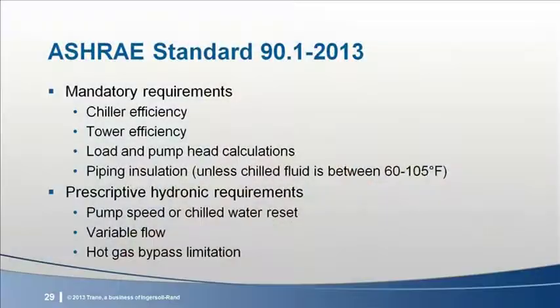Next up, load and pump head calculations. How do you do your pump head calculations? We hope you're using something like Trane Pipe Designer software. We have heard lots of crazy ideas about how to size pumps, like the height of the building times 2. We don't recommend this, and neither does the code. It's actually a requirement of 90.1 to use generally accepted engineering practices for calculating not just load, but also pump differential pressure for the purposes of sizing the pumps.